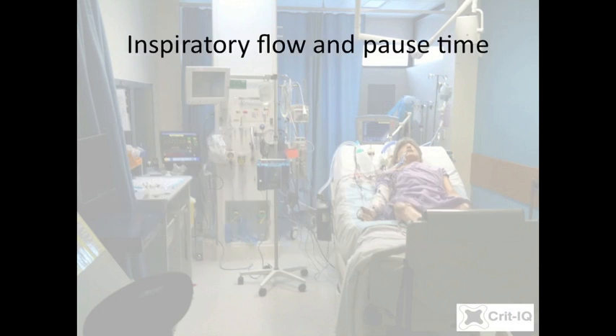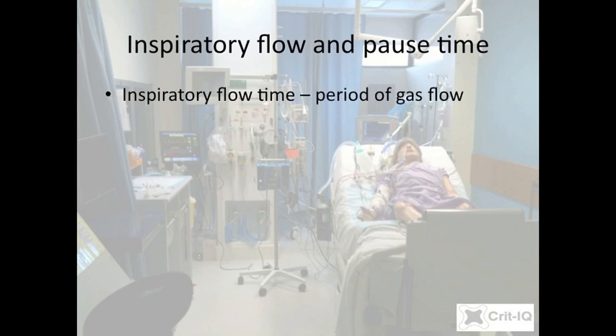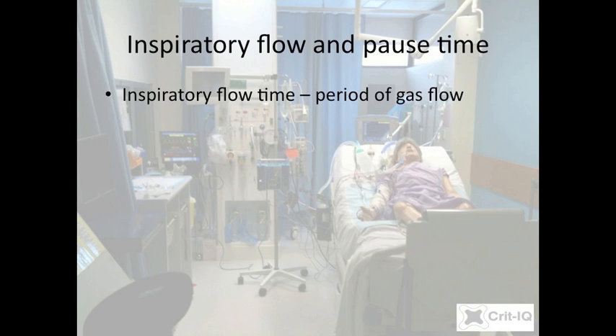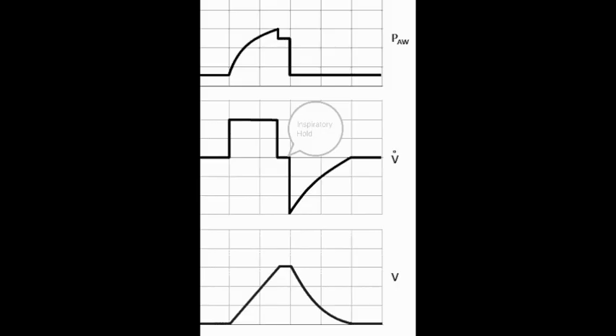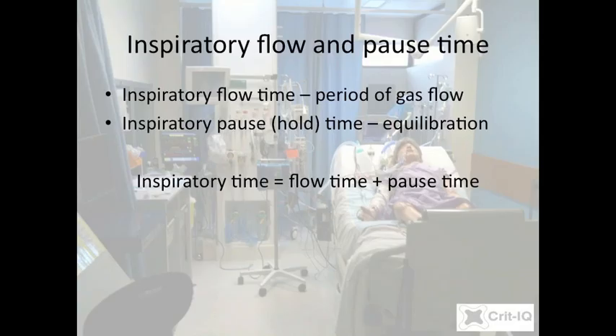Inspiration can also be split into two distinct phases. The first, called inspiratory flow time, is the phase in which gas is actively flowing into the patient's lungs. In the second, known as the inspiratory pause or inspiratory hold, all flow has stopped with the lungs inflated — this is thought to improve gas distribution within the lungs. Inspiratory time is the sum of both inspiratory flow time and inspiratory pause time. For practical purposes, the default settings are more than adequate for most patients.